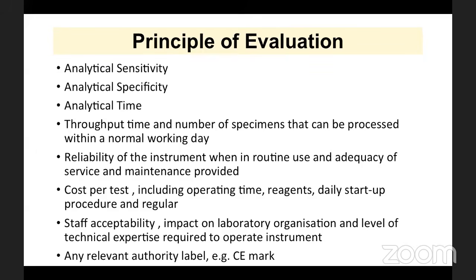And we are charging the patient 100 rupees, it is okay. But remember one thing, in this cost per test, you include operating time, other reagents, cost of control, cost of calibrator, and also include cost of your CMC or AMC, and also include cost of your machine. Suppose life of machine is 5 years, and you're taking AMC, then you see how much cost you can attribute to machine cost, how much cost you can attribute to CMC, how much cost you can attribute to calibrator and control. Then you decide cost per test.